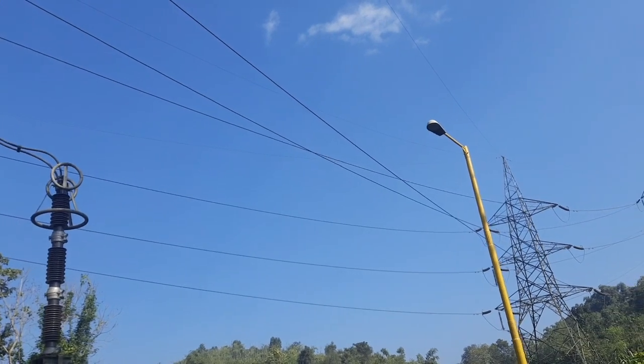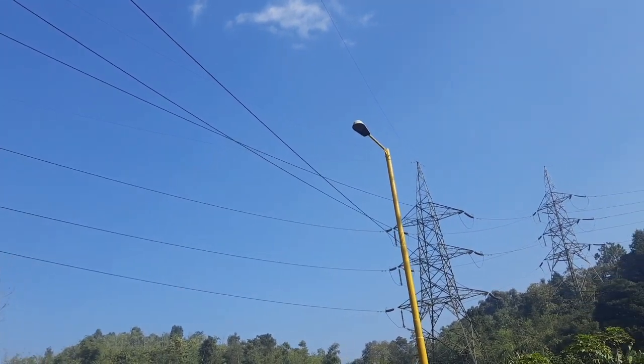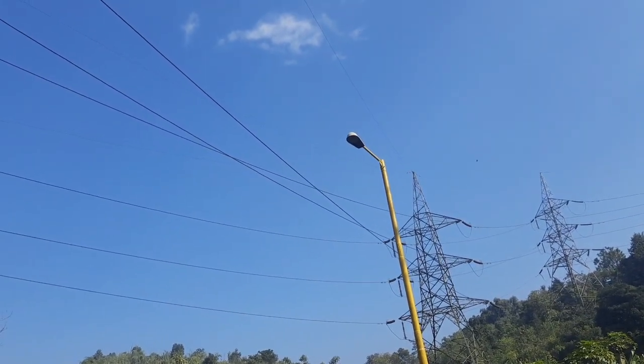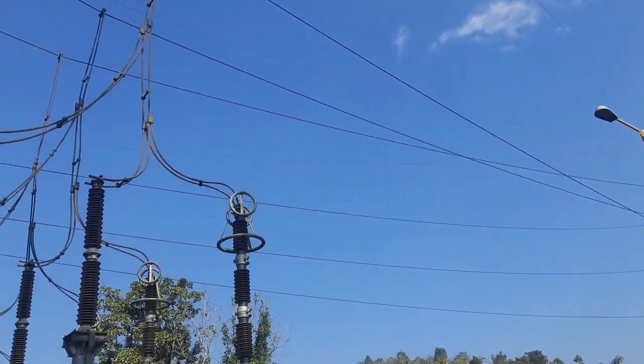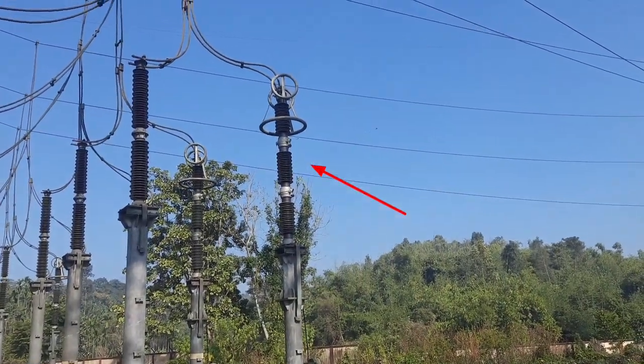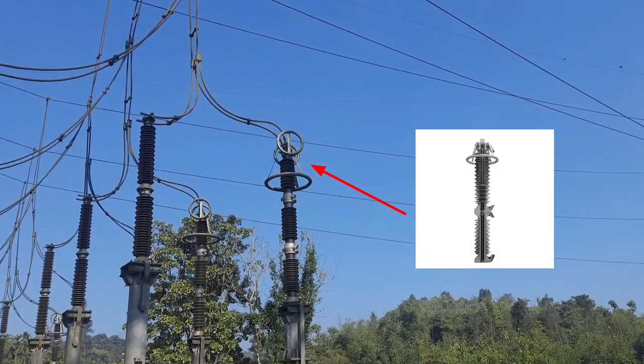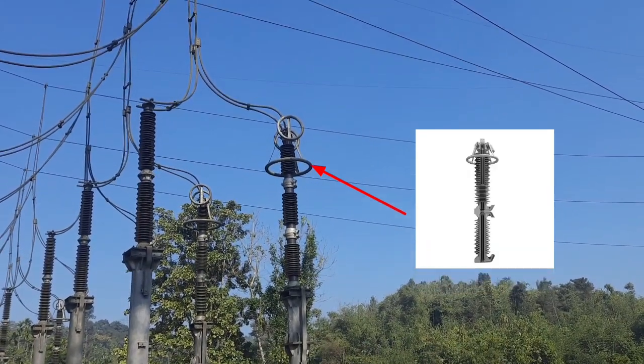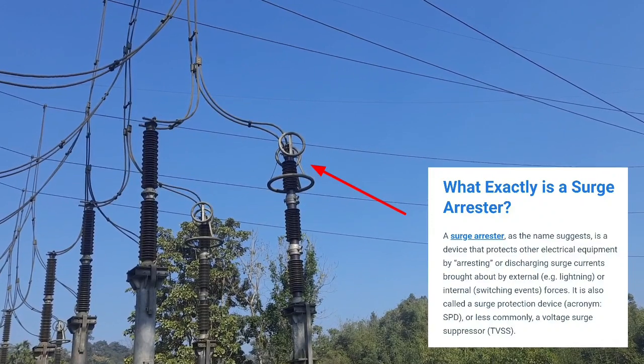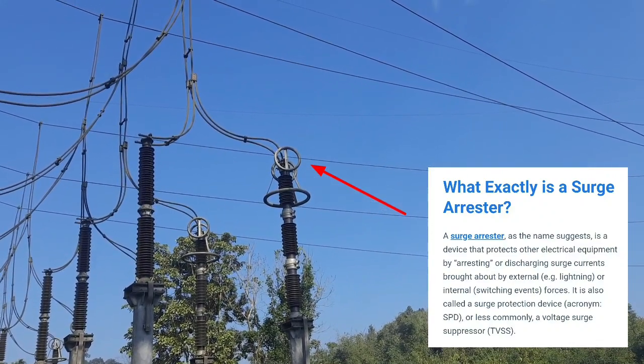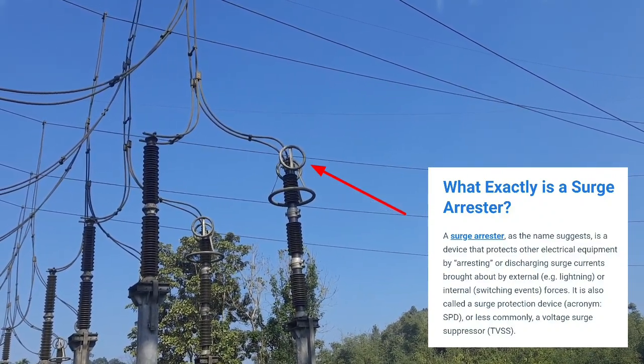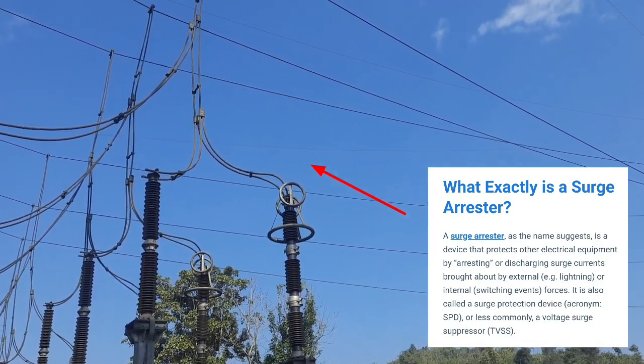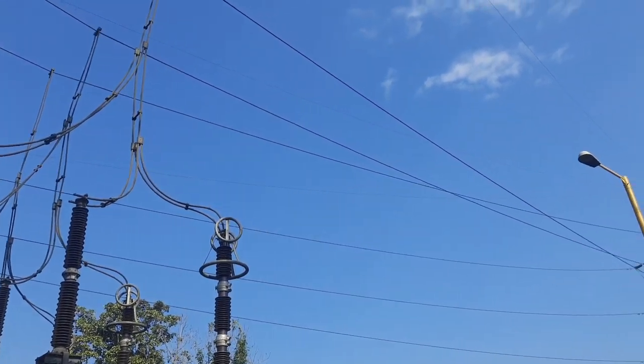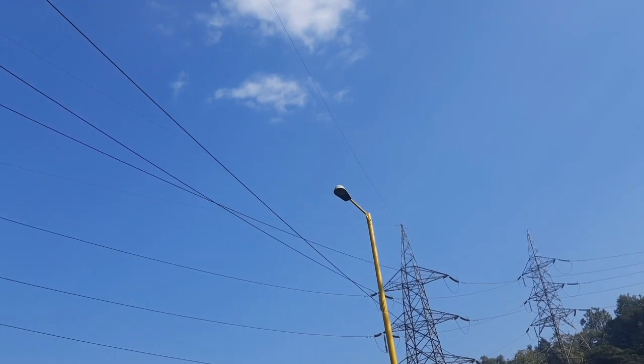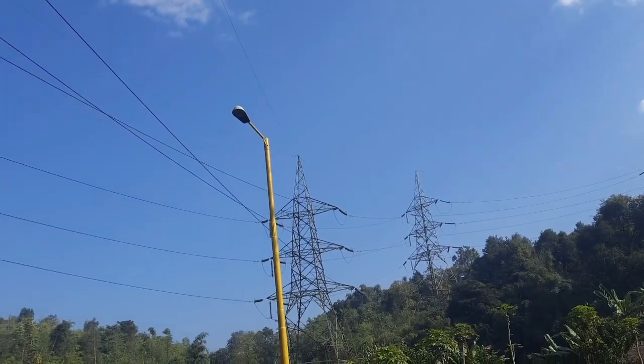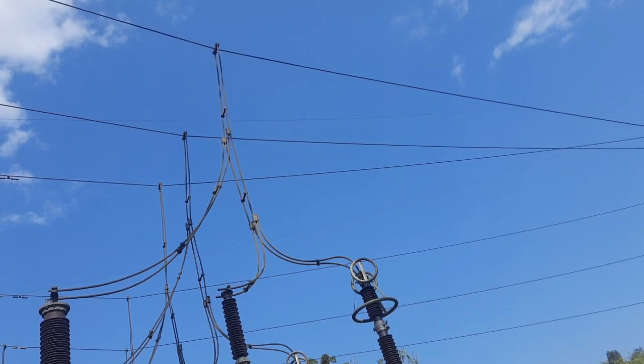In every transmission line, whenever the transmission line enters the substation, the first element, or the first line of defense, is your surge arrester, which is this. You'll see the rings on top. The purpose of this is that whatever surge is there in the transmission line, especially during switching operations, which is where 90% happen, or on a rainy or stormy day, or on a cloudy day, if there is any possible surge, that surge will be diverted towards the earth.